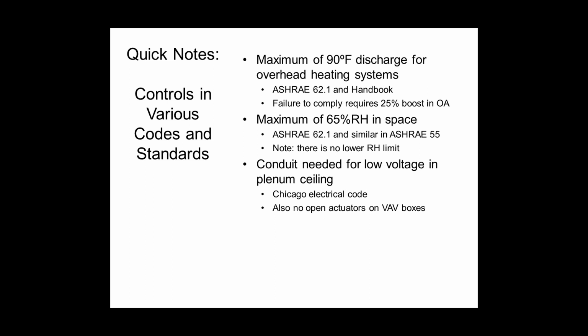Additionally, you can't have any exposed wiring in the plenum, obviously, so your VAV controller can't just hang on the side of the VAV box like we do in every other city. It's got to be in a NEMA enclosure, right? It's got to be an electrical enclosure also.